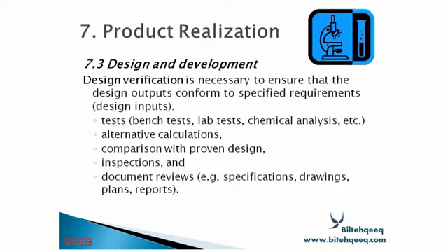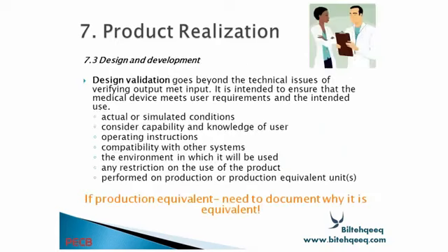And now we will talk about design verification, which is necessary to ensure that design outputs conform to the specific requirements. Design input, test, bench test, lab test, chemical analysis, etc. Alternative calculation, comparison with proven design, inspections, document review, for example, specification drawings, plan, and reports.